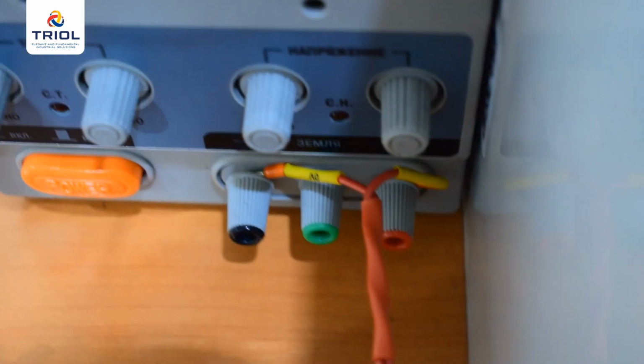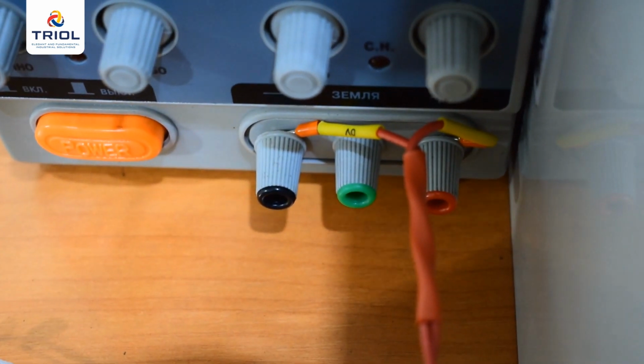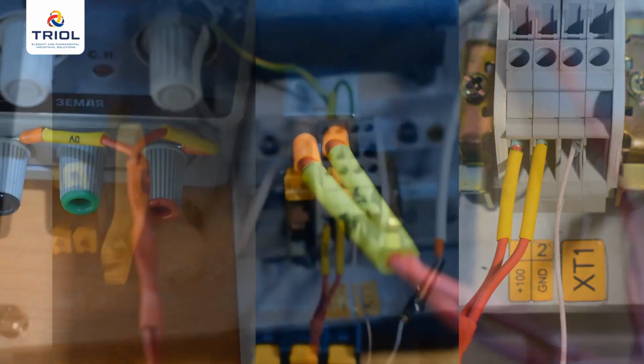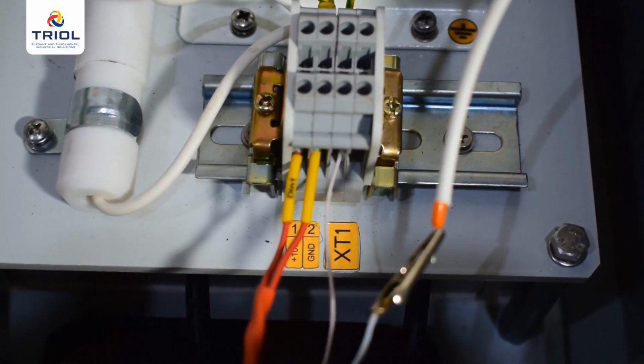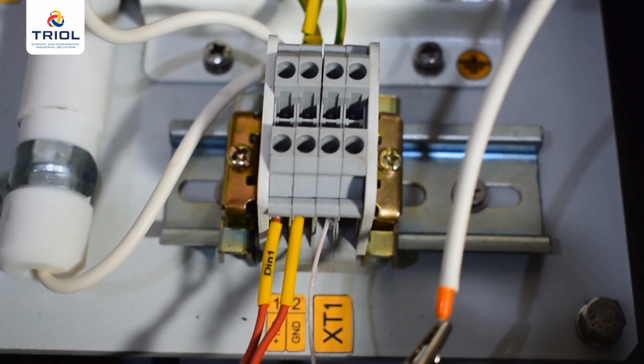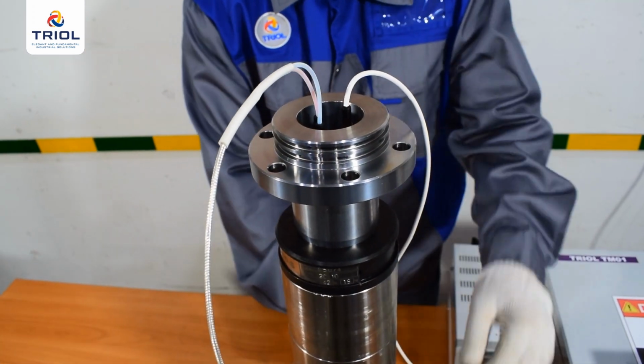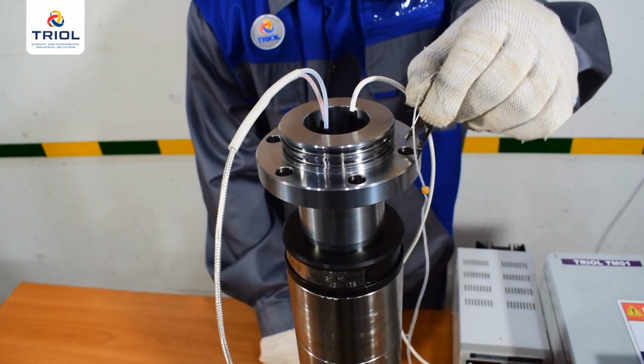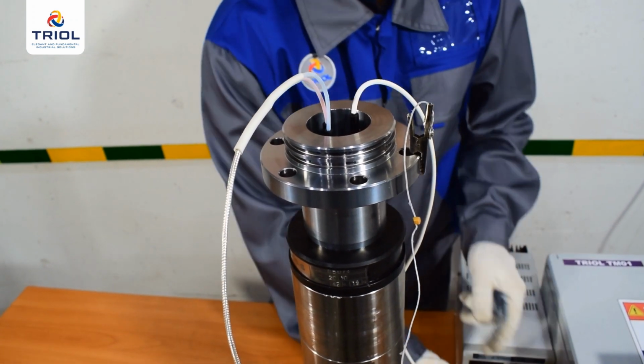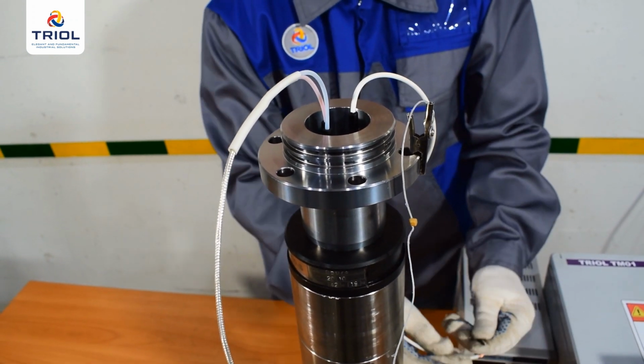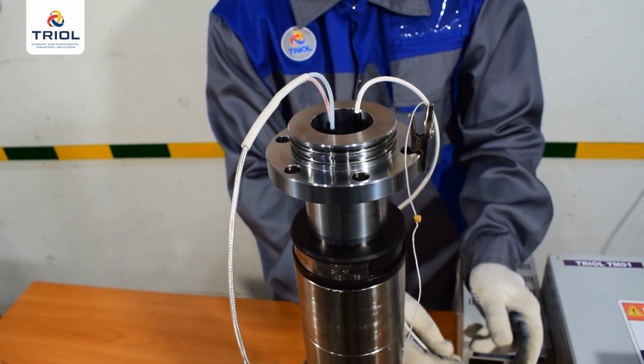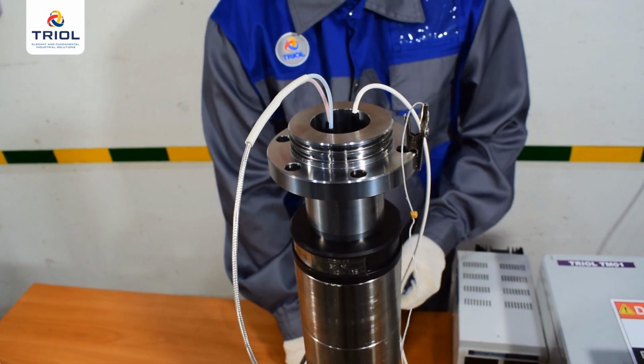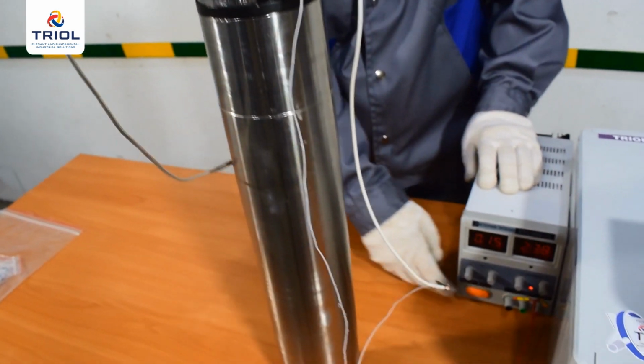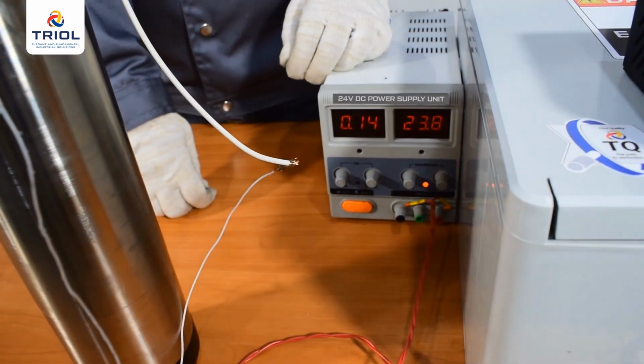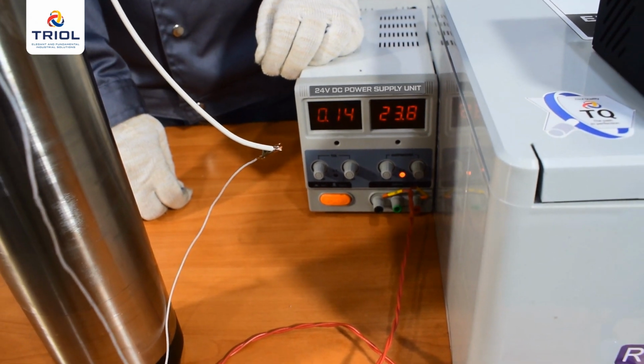Connect the 0 volt plus 24 volt connection wires to the power supply unit, and on the other side to the corresponding contacts of the surface card. Contact markings are indicated on the surface card. With the TM01-10-S power wires, connect the GND to the Triol surface card and connect contacts to the marked contacts XT1 and the high voltage choke 1, 2. Lead 2 wires with alligator clips at both ends to the corresponding contacts of the XT1 high voltage choke.